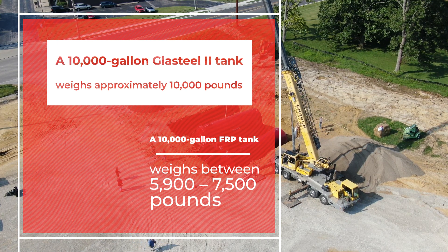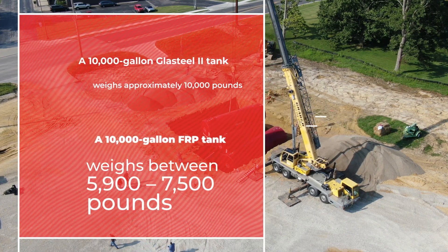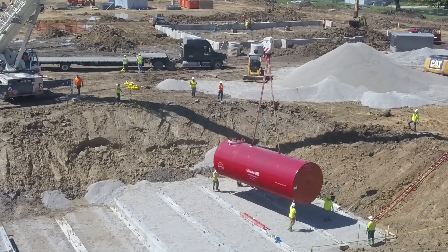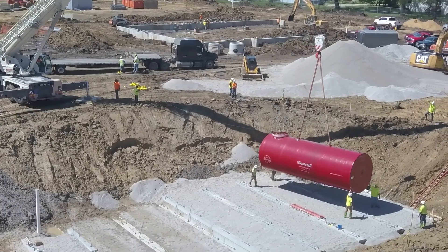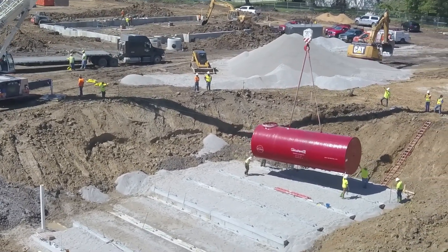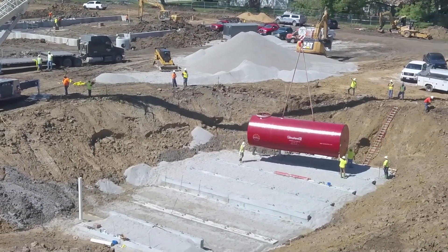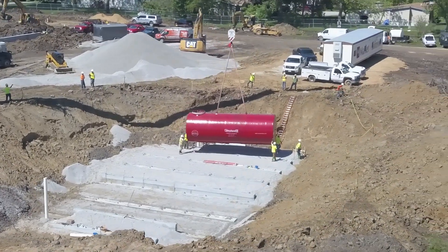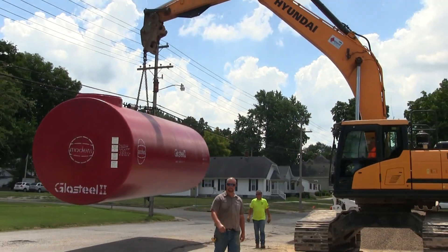A 10,000-gallon Glasteel II tank weighs approximately 10,000 pounds. A 10,000-gallon FRP tank weighs between 5,900 and 7,500 pounds. Be sure to consider crane setup, location, and reach over into excavation for tank placement, and never drag or drop a storage tank. Though tanks may look the same, their weights are very different. Be sure to check the bill of lading for estimated weight or call the tank manufacturer. Do not drop or roll a tank.